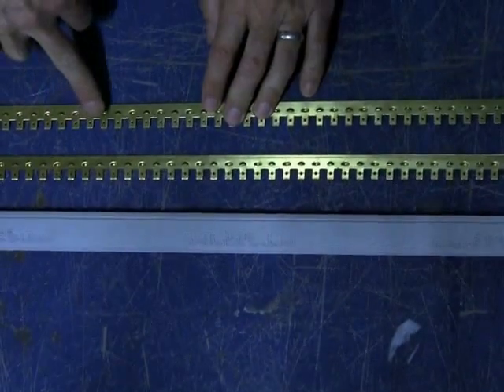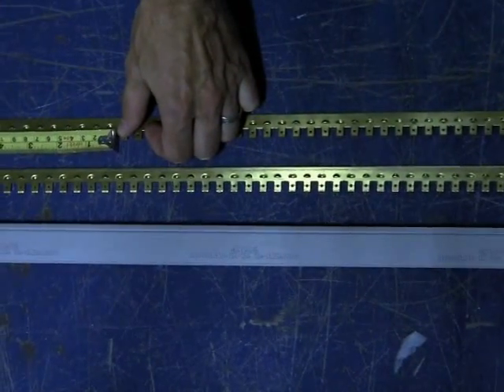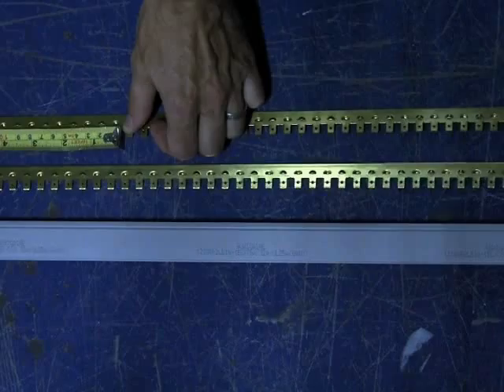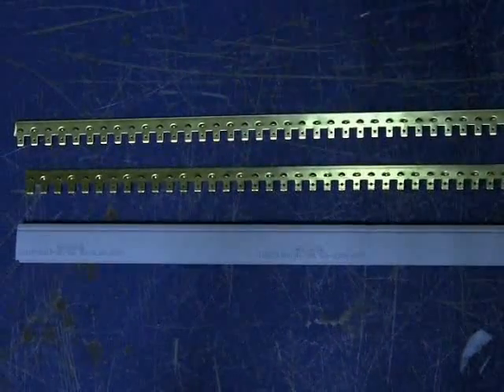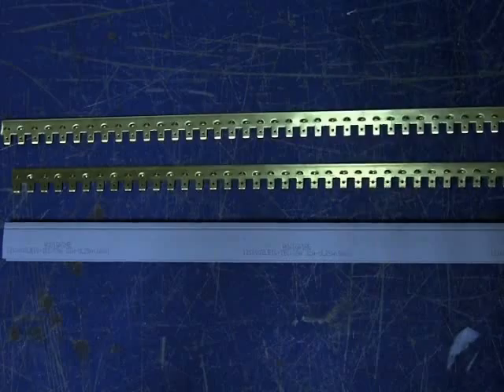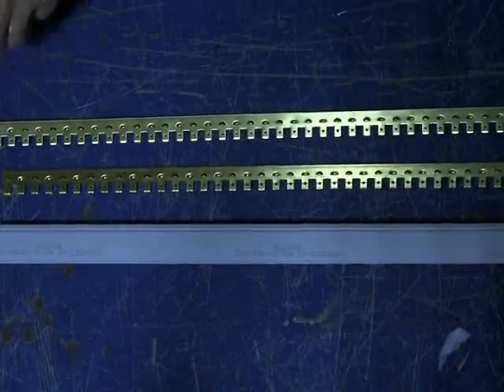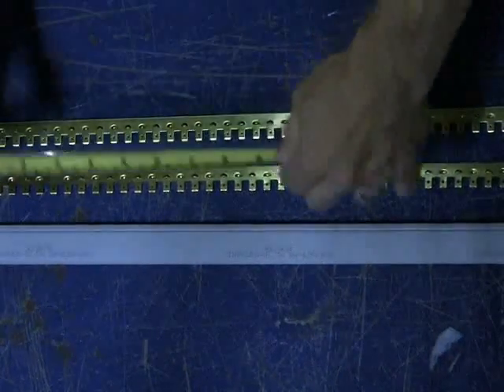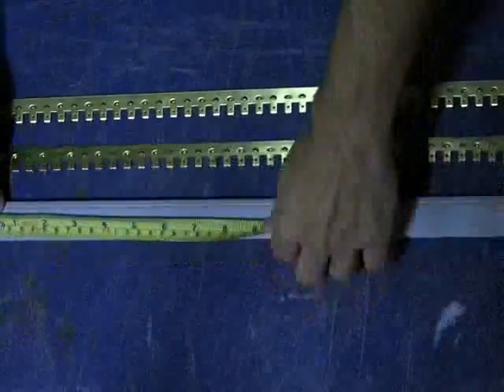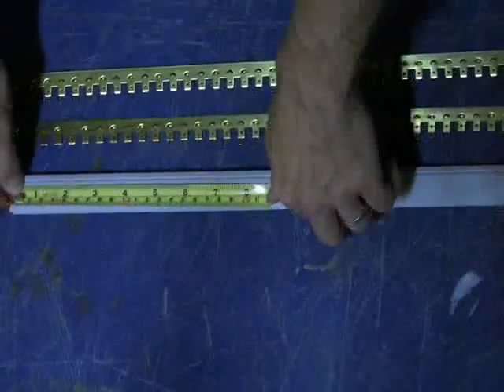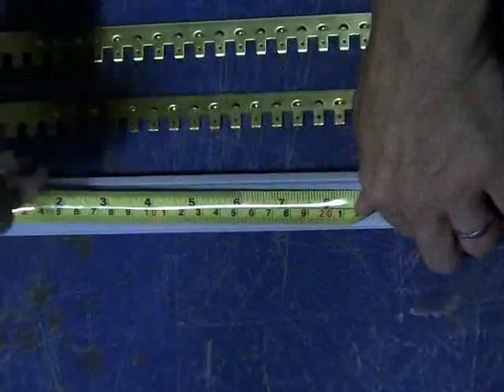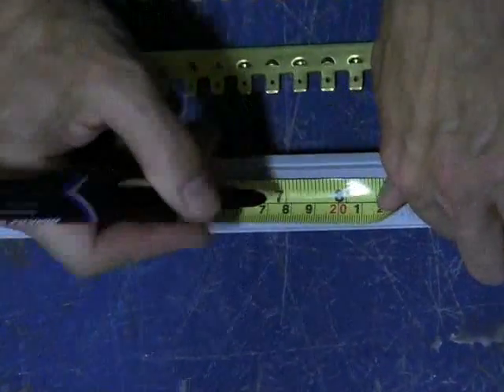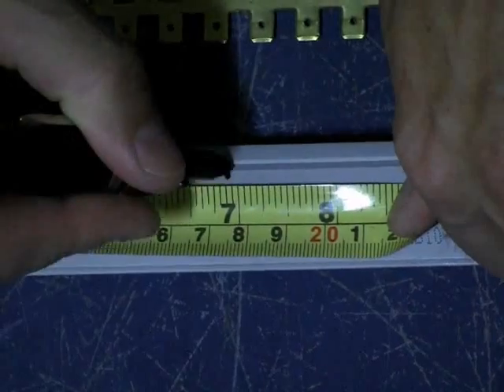Now, count the number of tabs you need. In this case we're counting 12. Measure the length. Add 30 to 40 millimeters to account for the end supports. Mark the insulation. Now you're ready to cut.